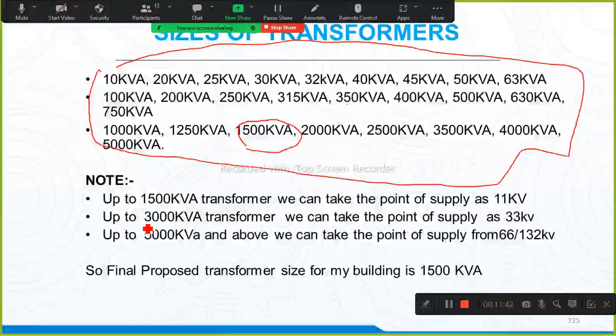Now, how do we decide what point of supply has to be taken for this building, for this load? So what is the condition given? If your transformer size is up to 1500 kVA, अगर आपका transformer size 1500 kVA तक रहेगा, so we need to take the supply from 11 kV point of supply. If your transformer size is from 1500 to 3000 kVA, we need to take the supply from 33 kV point of supply. If your transformer size is more than 3000 kVA, up to 5000 kVA and above, we need to take the supply from 66 or 132 kV supply line.